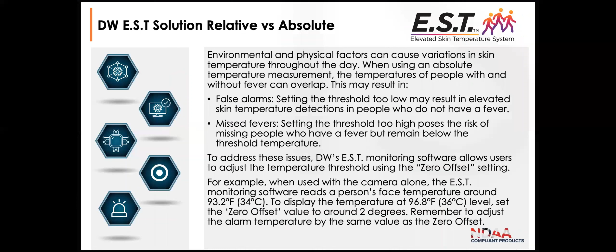It's relative versus absolute - whether you're setting it too low or too high, too low you get false alarms, too high you're missing readings. Within the software itself, you have an offset capability so you can make adjustments, raising or lowering it in the software settings for that particular location. The process, which we get into in other videos, involves using a medical grade thermometer to do a comparison and set that offset based on the people coming through that particular location.